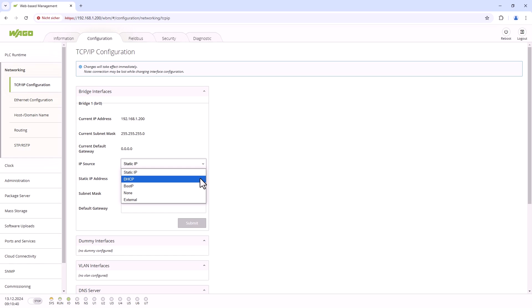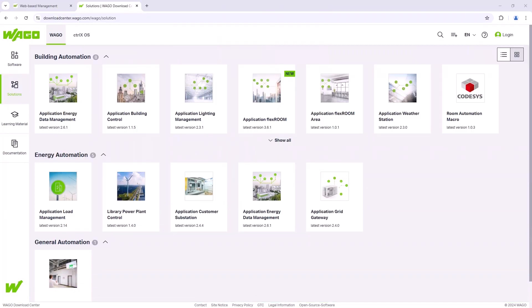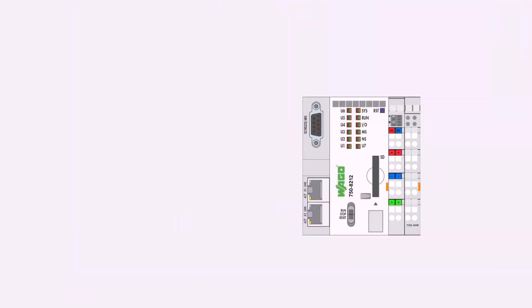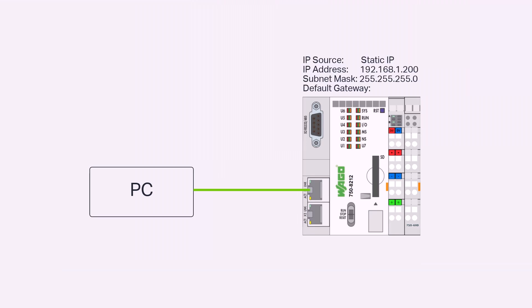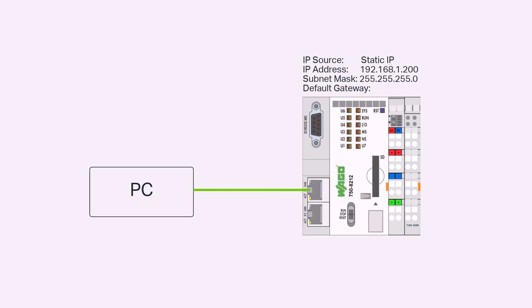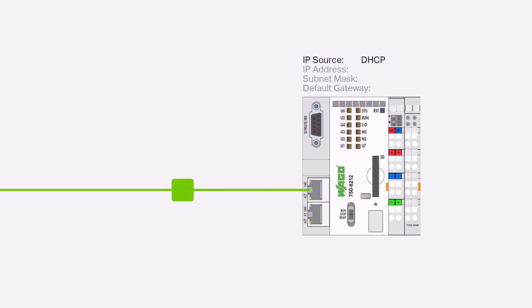Especially in an industrial environment, static IP addresses are often used at the network level of the controller. However, even when installing an application on the controller, depending on the network structure and policies, it may be helpful to first connect the controller directly to the PC, assign a static IP address, install the application, and then if necessary, switch the controller back to DHCP and integrate it into the target network.